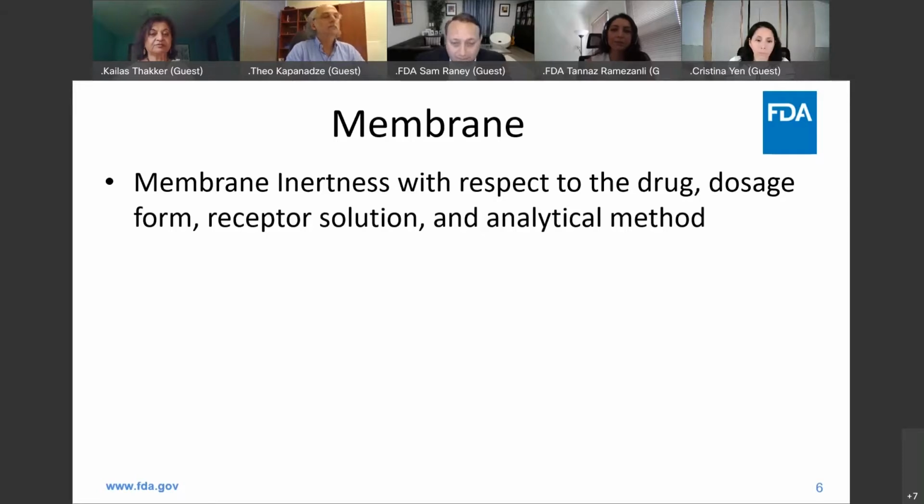Well, I can tell you what my thought is. In my experience doing this, sometimes with the cellulose membrane, cellulose acetate membranes, if you've got some strong organic solvents, the membrane just clarifies, and you can tell something's gone wrong here. So I think that from a chemical compatibility issue, what I want to be careful here is that we're not creating a mountain out of a molehill, and now you've got to submit data for things and do additional studies. The thing is that the operator just needs to be aware of what's going on.